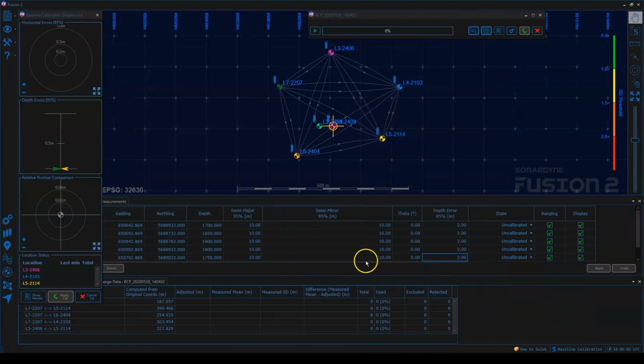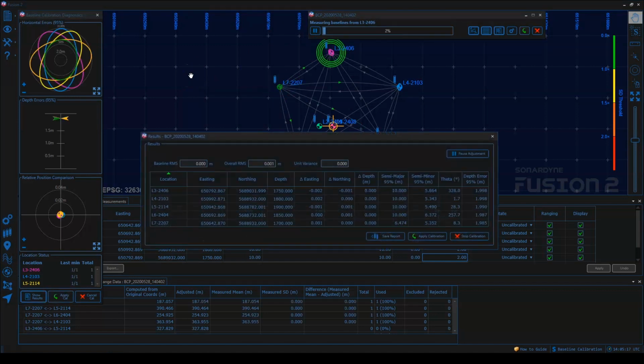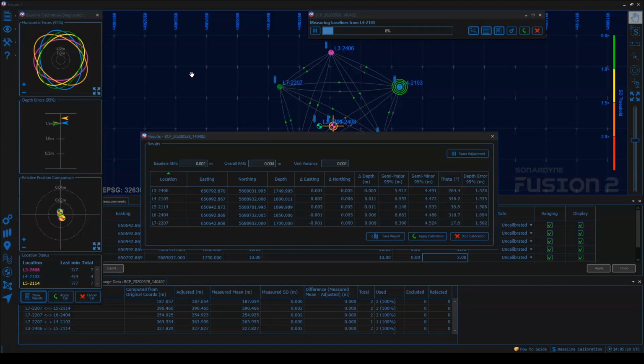to bring up the calibration bar and the baseline calibration diagnostic window. We can click on the play button in the calibration bar to start the process, and we have nice clear graphics to show us what baseline it's collecting at that time. As soon as the first round of data comes in, the results table opens up and we can see the software begins to refine the start positions. The real benefit here is that if we see the positions change dramatically, we know there's a problem. These are highlighted in bold orange text.